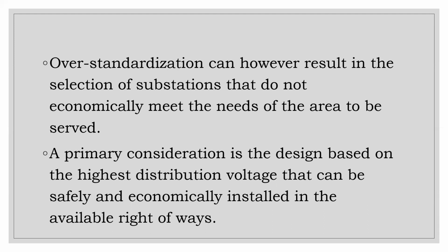All right. Now, one primary consideration is based on the distribution voltage. Remember, we said that voltage, and I had it at the top there. Voltage is one of the key factors in deciding on the layout of your substation. Right? And the highest distribution voltage that can be safely and economically installed in the available right-of-ways.